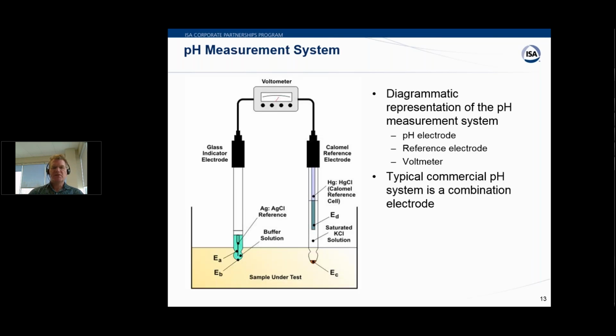And so that's the measurement system as we see here, right? We have the indicator electrode on the left where we have the voltage across that measuring membrane, and then we have the saturated solution, which is the reference, on the right, and then we measure the voltage between the two electrodes, and of course the hydrogen ions in our sample under test are what complete the conductive element in the liquid. Okay, but because this is cumbersome and expensive to have multiple electrodes, we typically on a commercial system use something called a combination electrode, which we show on the next slide.